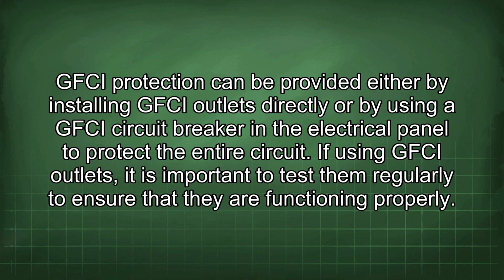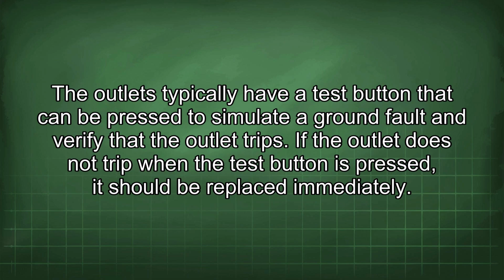If using GFCI outlets, it is important to test them regularly to ensure that they are functioning properly. The outlets typically have a test button that can be pressed to simulate a ground fault and verify that the outlet trips. If the outlet does not trip when the test button is pressed, it should be replaced immediately.